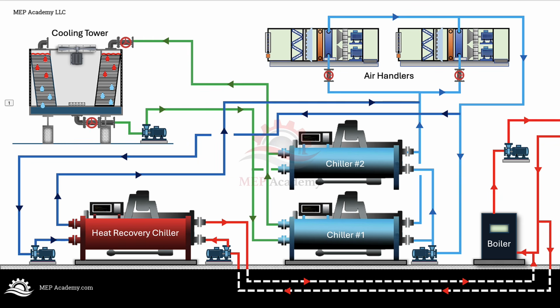The refrigeration cycle may be familiar, but the plant sequence can be more involved than a standard chiller plant. This is why heat recovery chiller systems need good design, good controls, and clear operating intent. Bigger is not always better. A heat recovery chiller needs somewhere to put the heat.